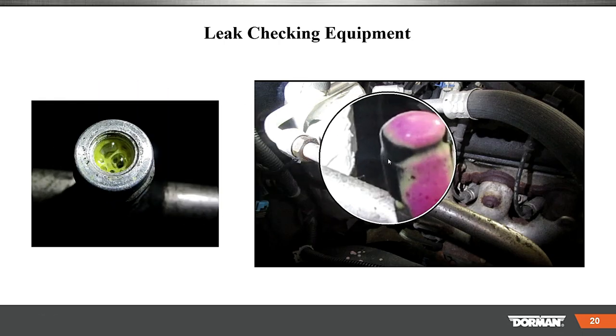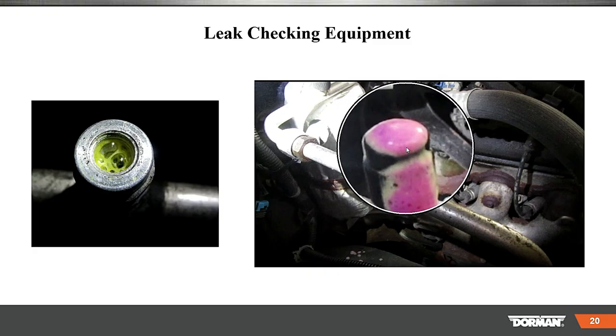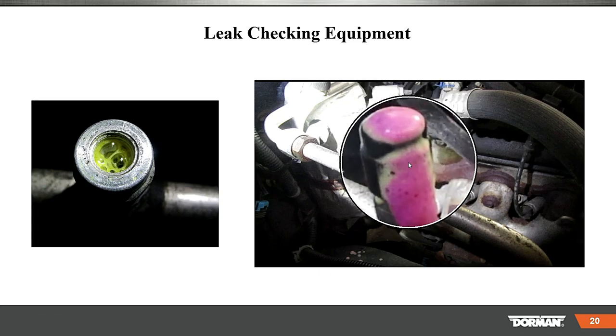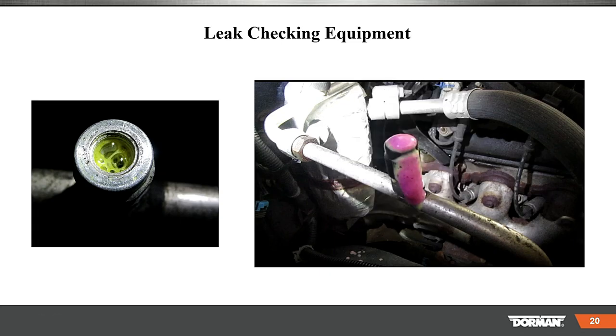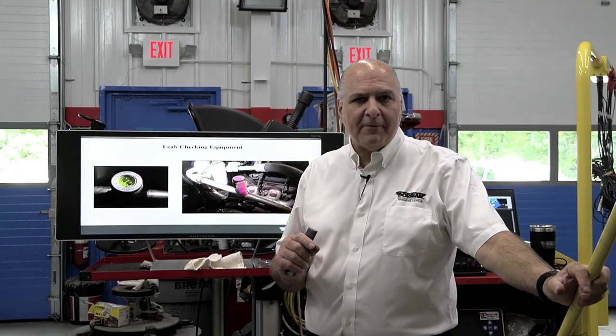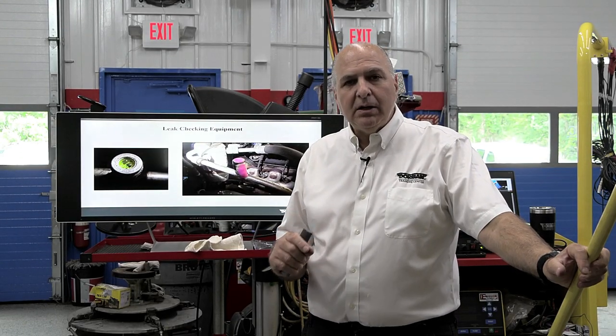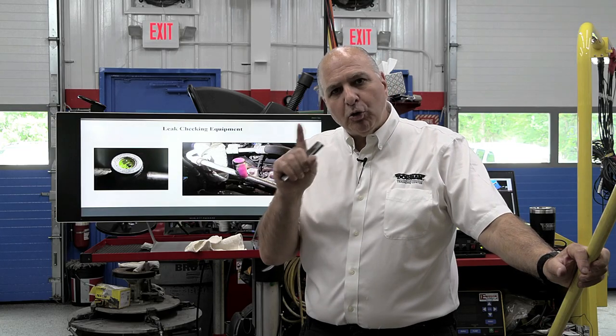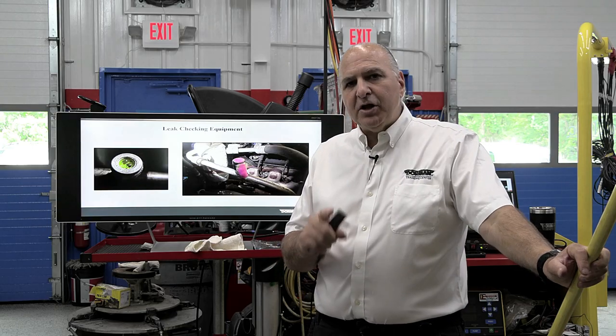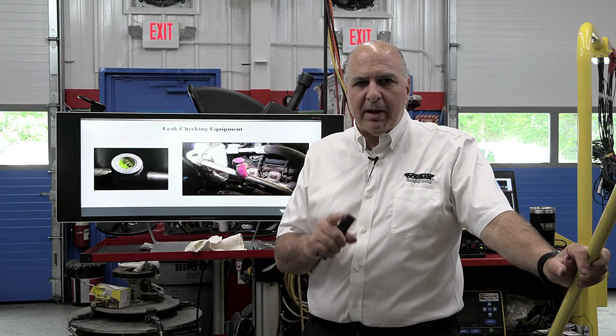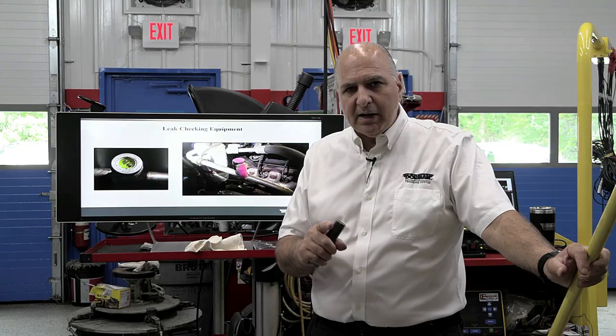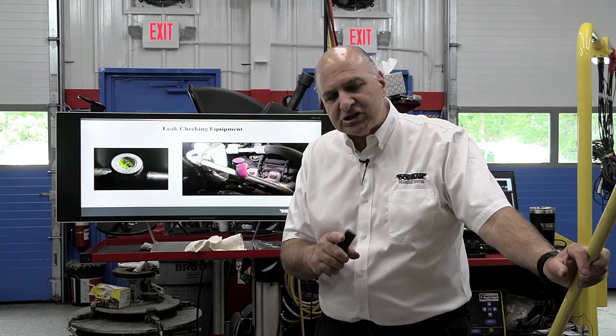Look at this one with the cap. With the cap, it had a leak. You see how the pink turned yellow? Right through the cap. Always get a good cap and lubricate the seal in the cap. Keep some Q-tips around and some clean POE oil, and lubricate it a little bit. Never use metal caps—they had problems with metal caps with adhesion, meaning two dissimilar metals stick together.